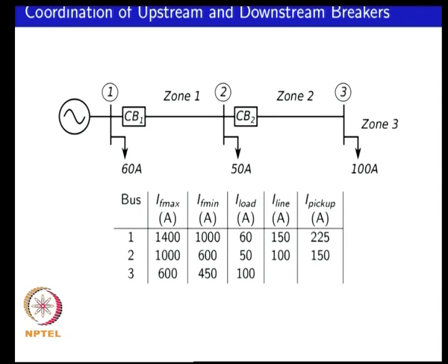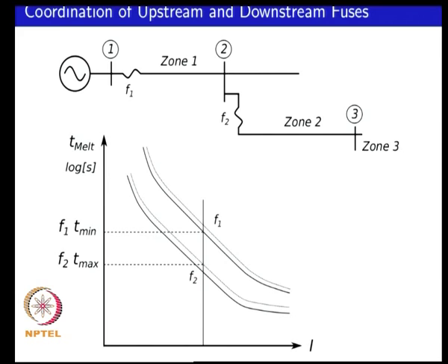In this example we looked at individual values of fault current levels — maximum and minimum — and examined the trip timings of the breakers. Another way to assess coordination is to plot trip time versus current and see where the curve lies. Software that performs coordination calculations can provide plots of time versus current coordination curves, giving a visual feel of whether coordination is achieved over a range of conditions.